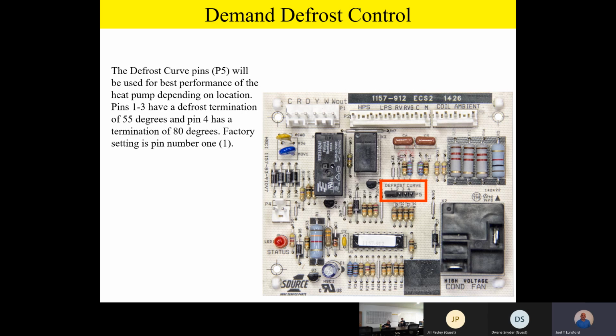Any questions or comments on the defrost curve and how we can change that in the field with a jumper selection? Any significant difference between the pin settings of 1 and 3, or are those all just the same, set at that 55, no difference in time, temperature, or anything like that?